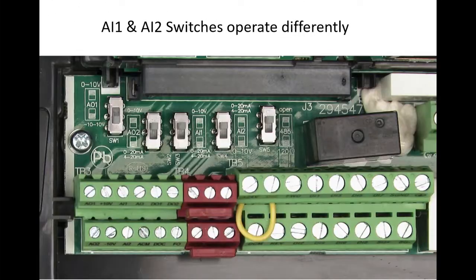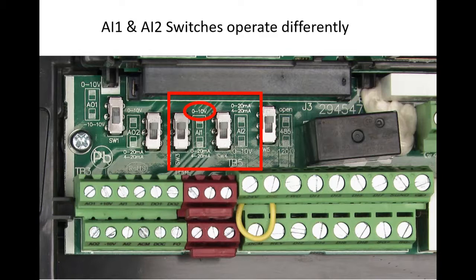The terminal board switches that switch analog inputs 1 and 2 between current and voltage are backwards from each other. Analog input 1 has voltage in the up direction and analog input 2 has it in the down position. So don't assume they both work in the same direction.